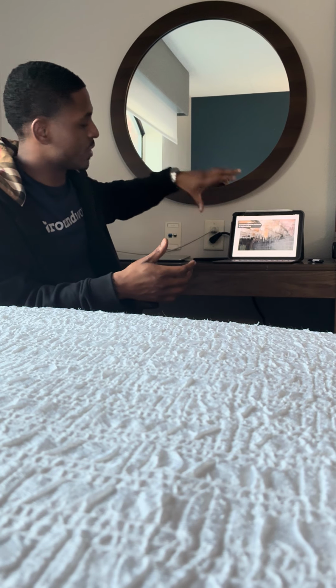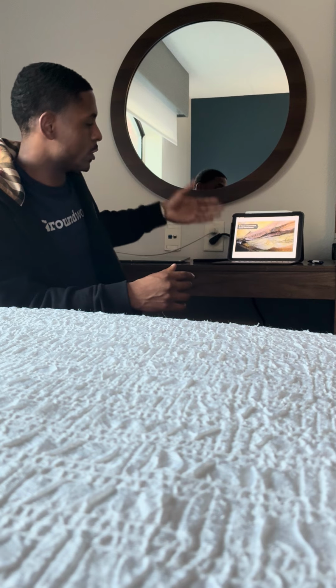Now, once the insulation becomes saturated, then you're going to start to see it sag and hang down where it's not going to be able to really hold any warmth in or actually do its job at all. Now, since right next to your insulation is your floor framing system, it's going to just transfer that water right over to the lumber next to it. So that's going to lead to very high moisture levels in your floor framing system, and that's going to cause organic growth over time. Ultimately, you end up with your R value completely compromised and a floor framing system that's decaying and an insulation system that's not holding in any heat.